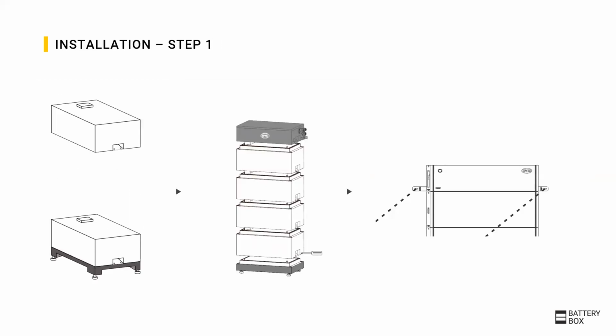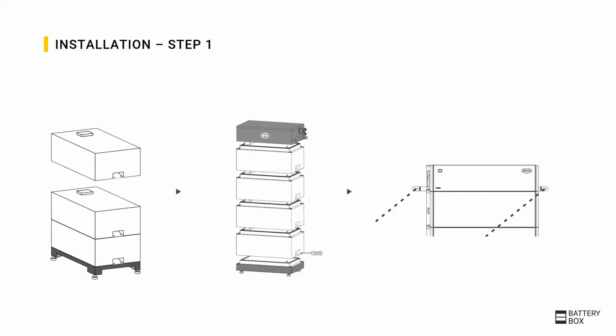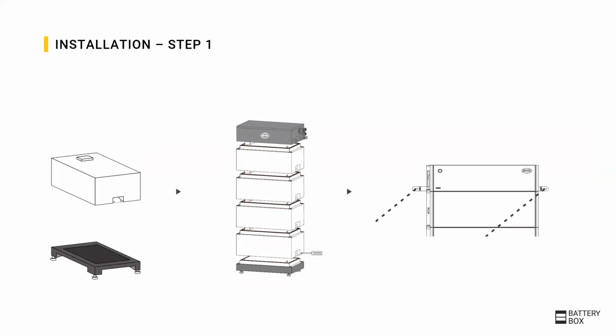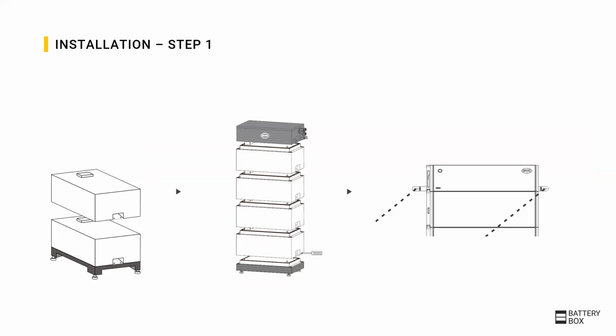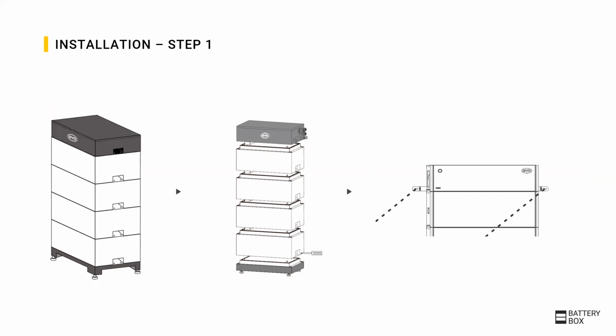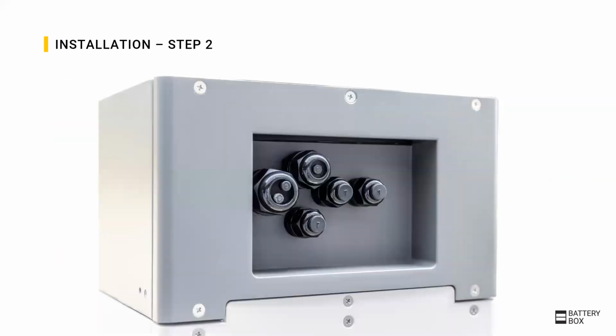With those limitations in mind, we look into the installation, which is held as easy as possible and which is shown in principle on this page. The base is placed on the floor and the modules are simply stacked on top without any internal cabling. The modules can then be fixed with screws on top of each other. Finally, the BCU is placed on the top module and attached to the wall. The next step will be the external cable connections on the left side of the BCU.